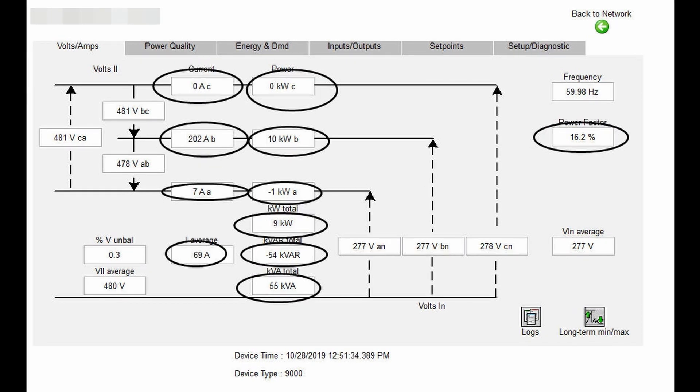And they not only did this — this was not my install or any company I'm associated with; this is something I was looking at for another facility and I just happened to notice it. But this is not only the way the contractor put it in — this is the way whoever was doing the setup in Power Monitoring Expert left it and said 'here you go.' The facility was unaware that it was this wrong and this far off until I pointed it out yesterday.